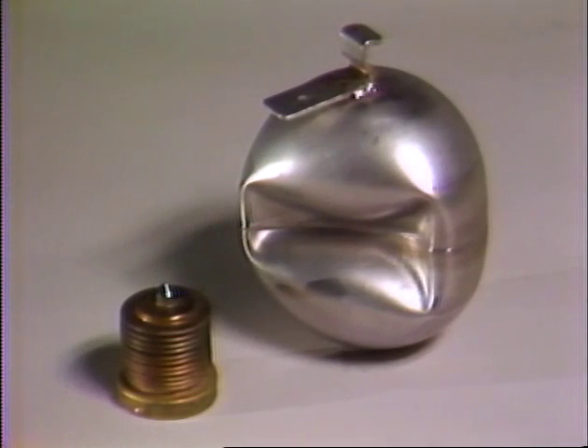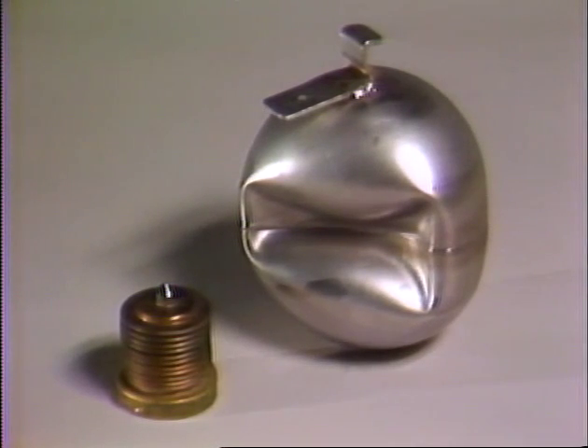Since both the float and the bellows element are relatively fragile, they can be ruptured fairly easily, causing the trap to fail. Most F and T's can be disassembled in the field for cleaning and inspection. Inspection will determine if the trap should be repaired or changed out.